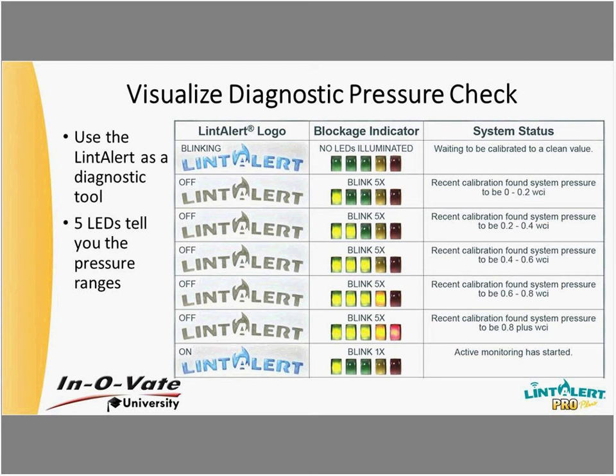Once we saw that happen, we realized the LintAlert logo was off, like you see on our screen, and the green LEDs blinked at us 5 times. That tells us a recent calibration was found, and there was between 0.4 and 0.6 water column inches of pressure. And that was true—we had 0.411 water column inches of pressure in that.